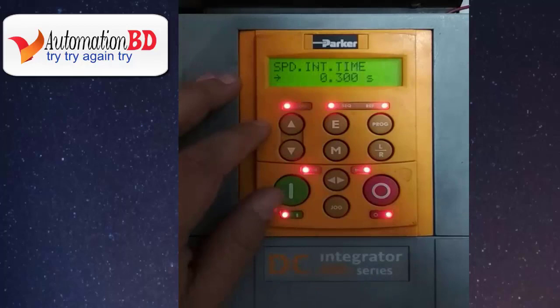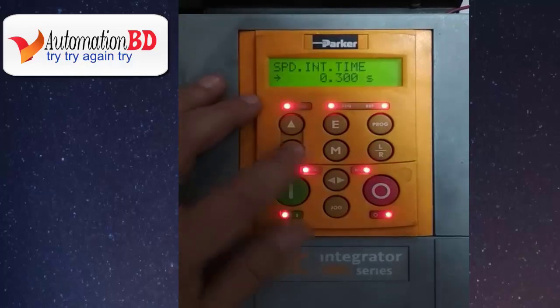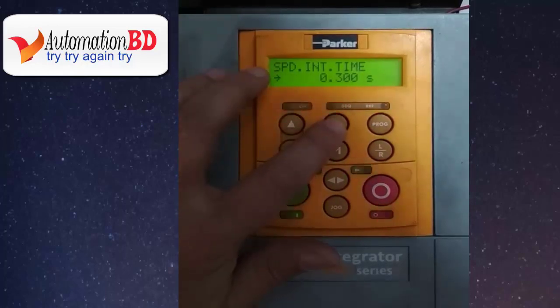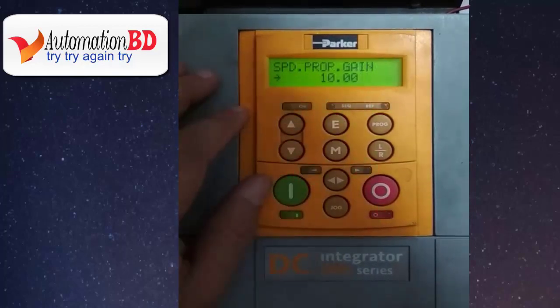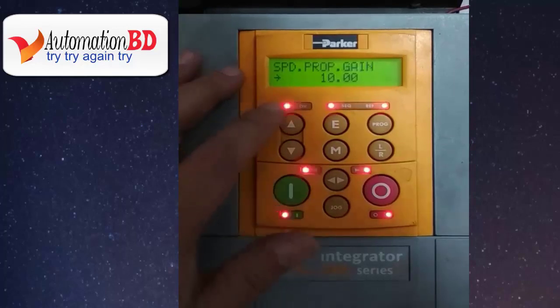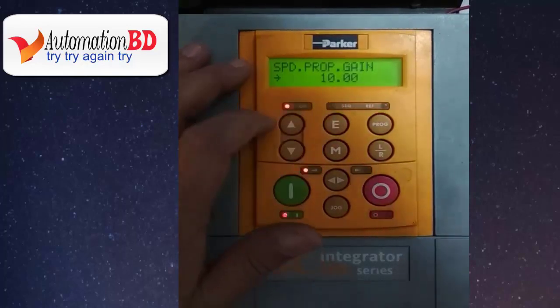Now you can see speed loop PI integral time adjustment — it is at the default value of 0.300 seconds. Press E. Now you can see the speed loop PI proportional gain adjustment. If you need to change it, do so; otherwise press E.